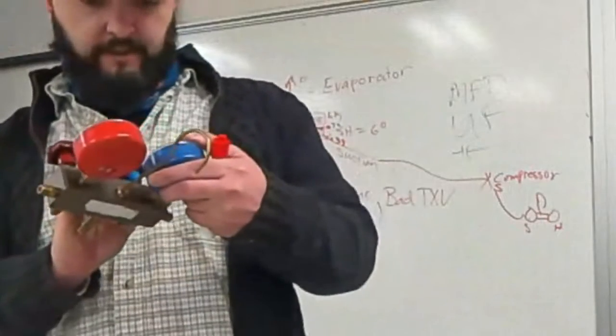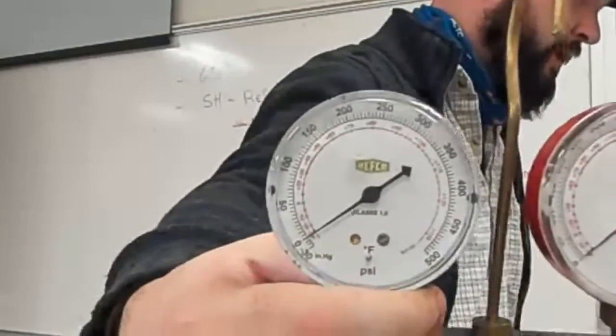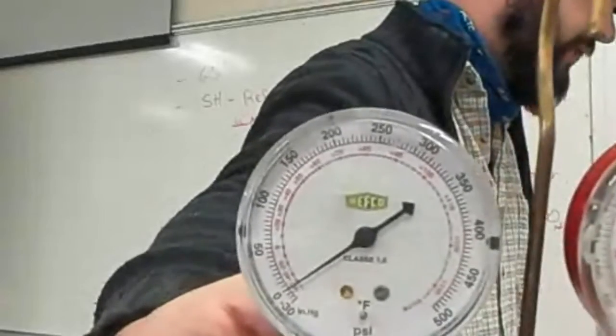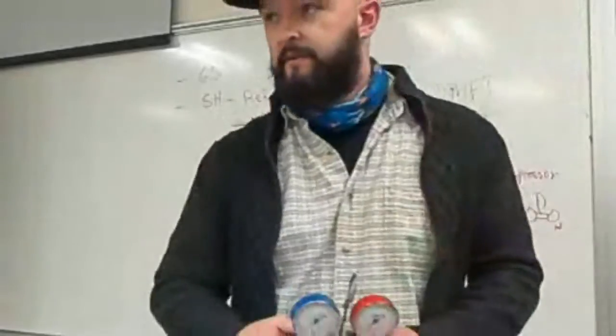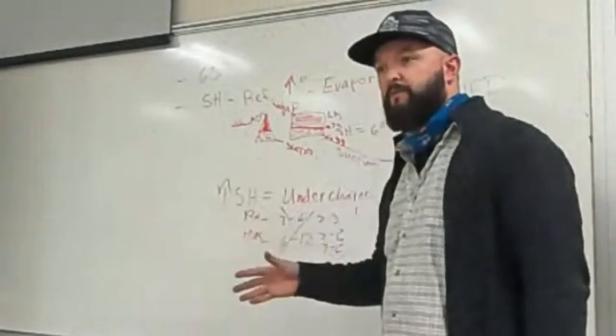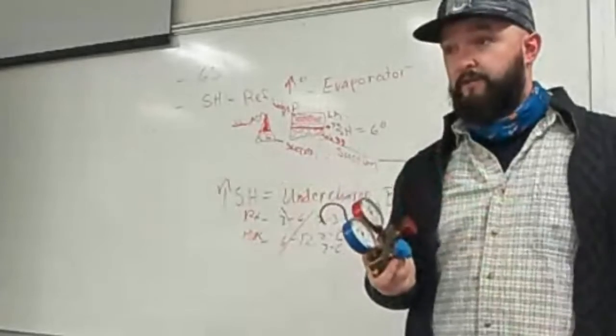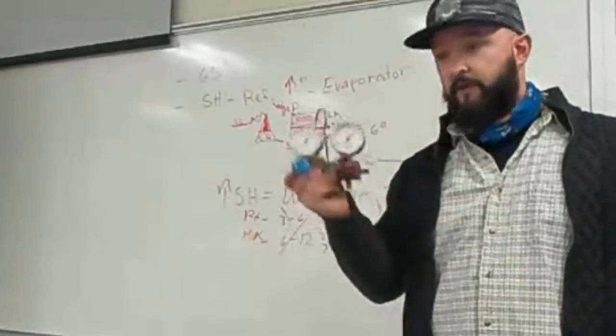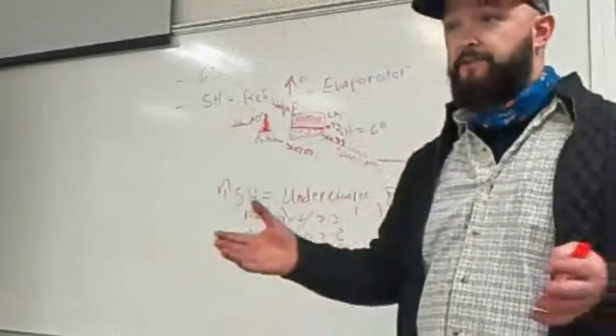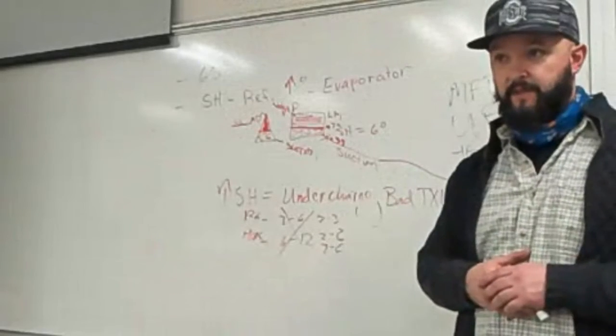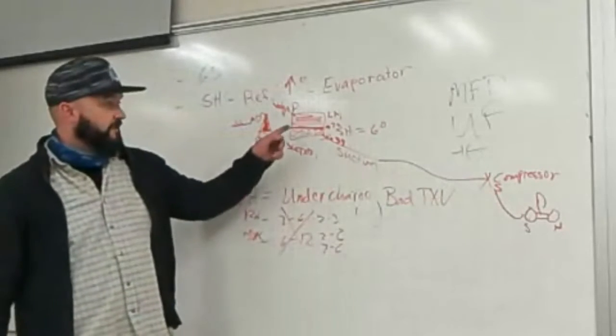So this gauge shows PSI in black and temperature in red. If we go to 100 PSI and convert that to saturation temperature, we're at 30 degrees on this coil. That obviously varies based on what refrigerant you have — that's why you have a PT chart. If you're using the correct gauges it'll convert it for you; it'll say R-404A or this one is R-410A. With digital gauges you can pick the refrigerant and it'll do the calculation automatically.